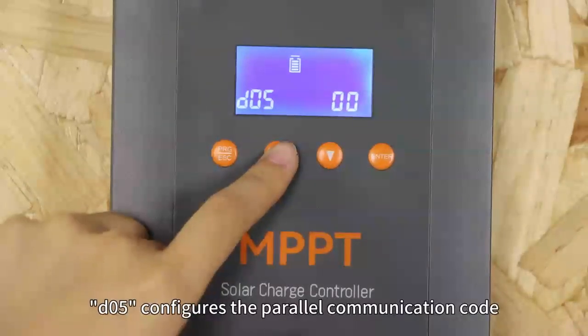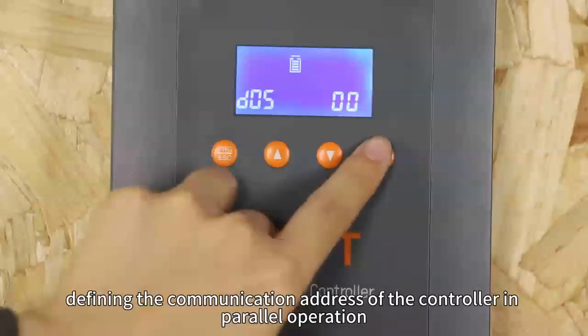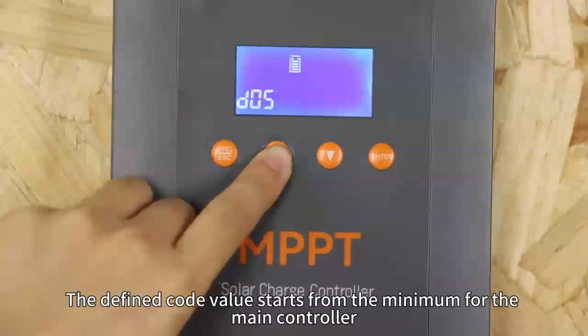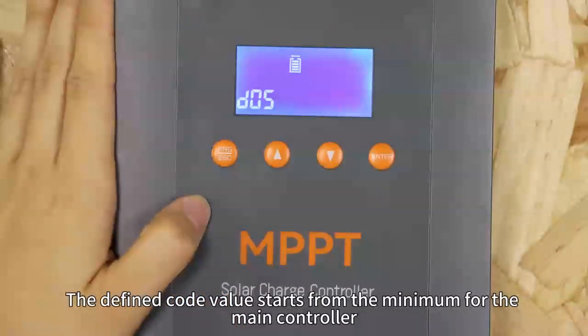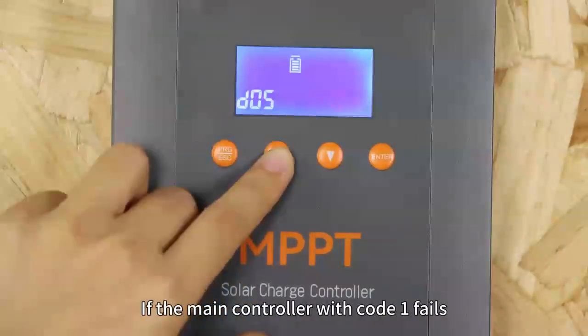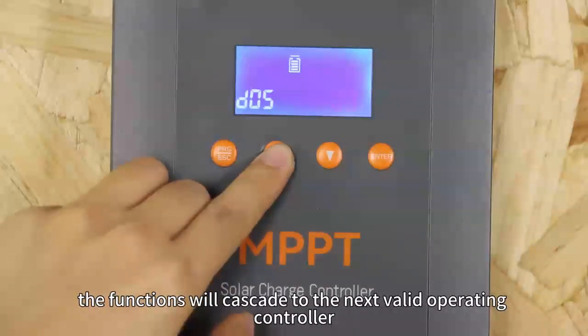D05 configures the parallel communication code, defining the communication address of the controller in parallel operation. The defined code value starts from the minimum for the main controller. If the main controller with code 1 fails, the function will cascade to the next valid operating controller.